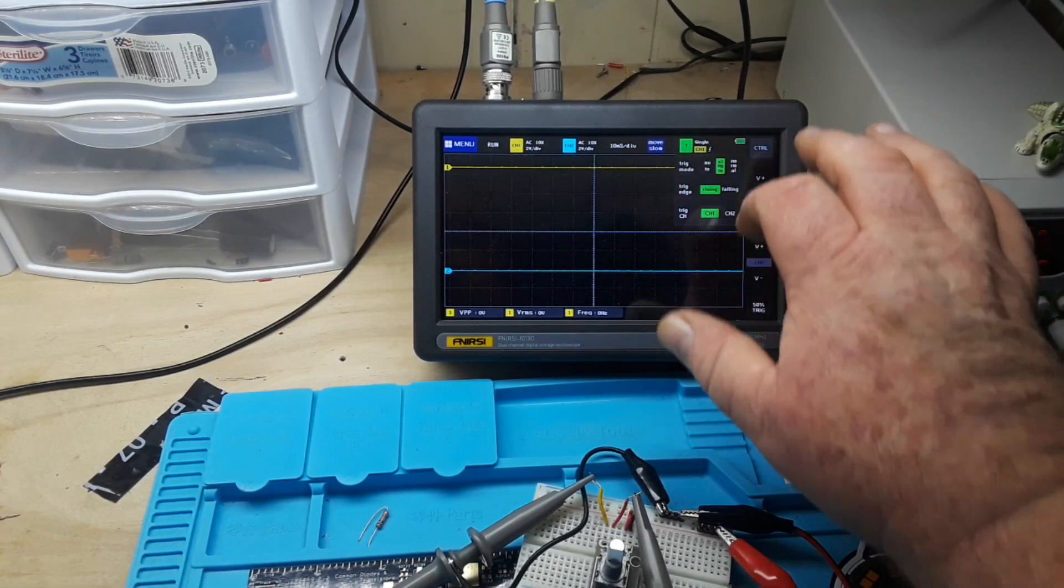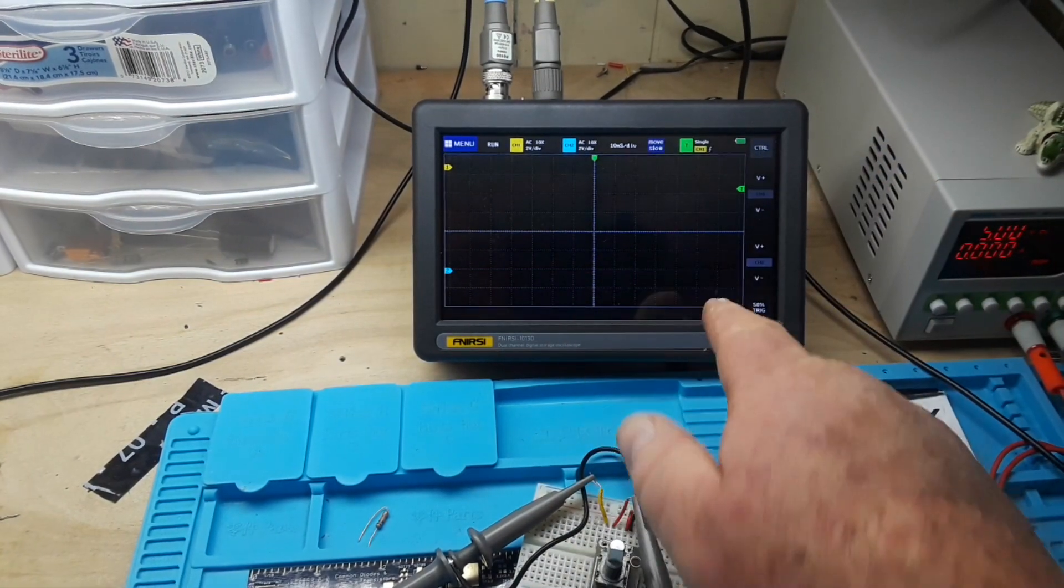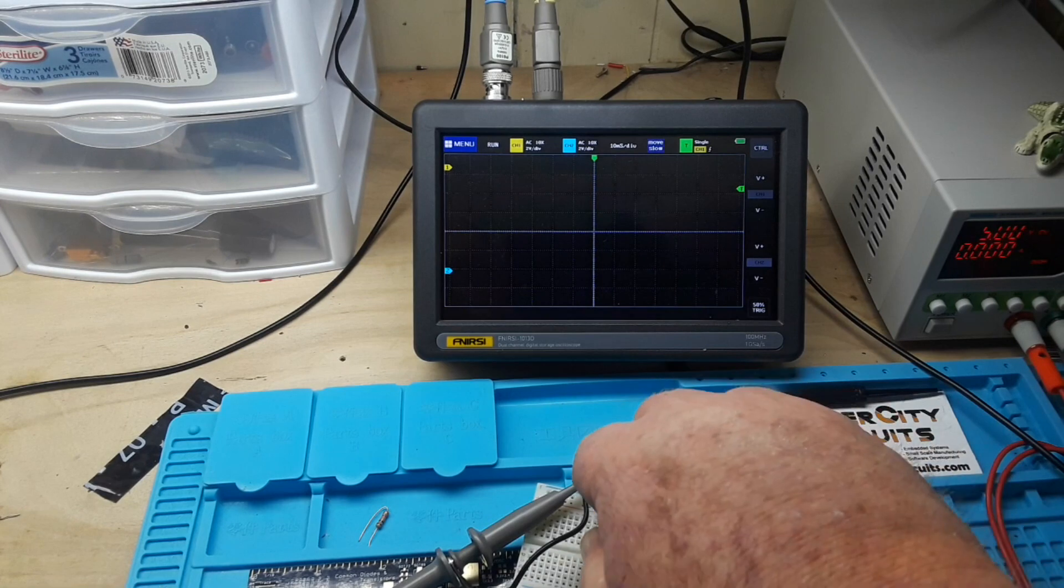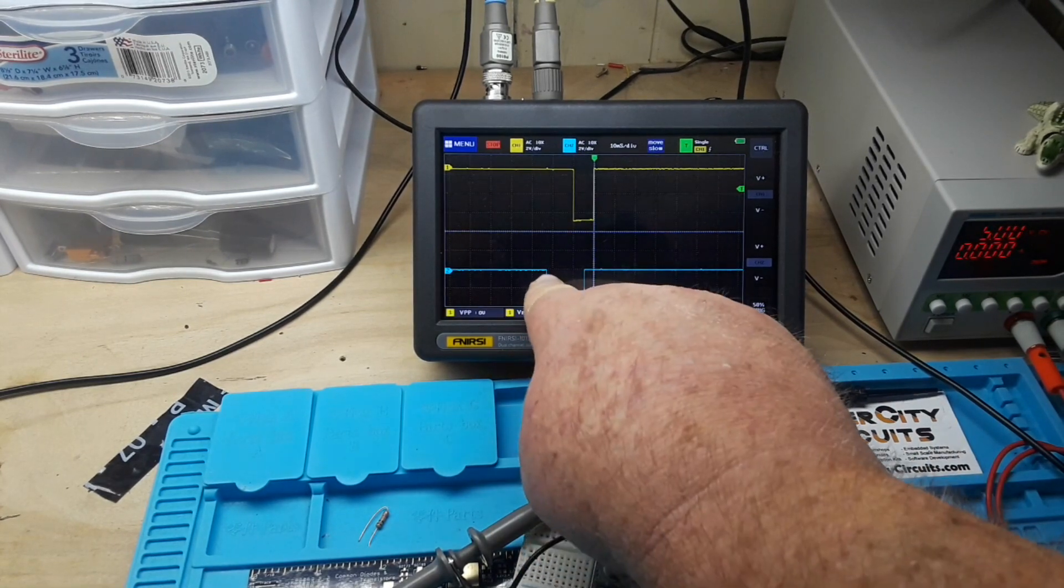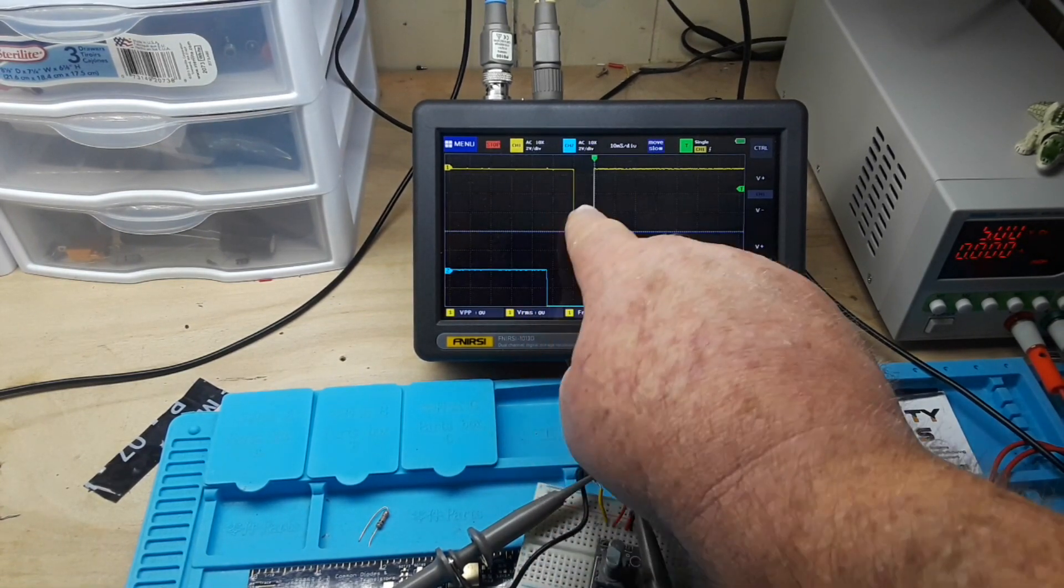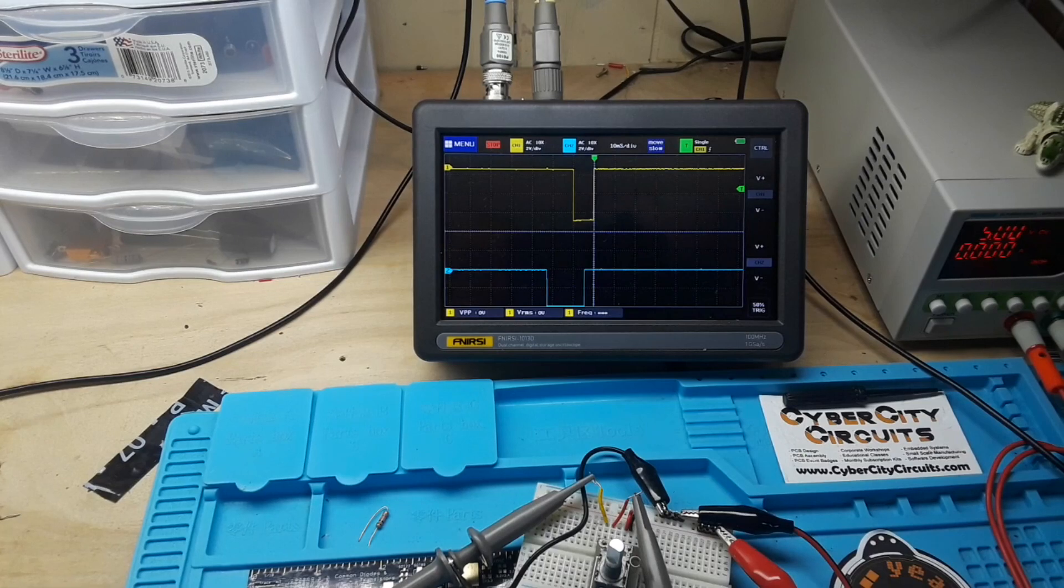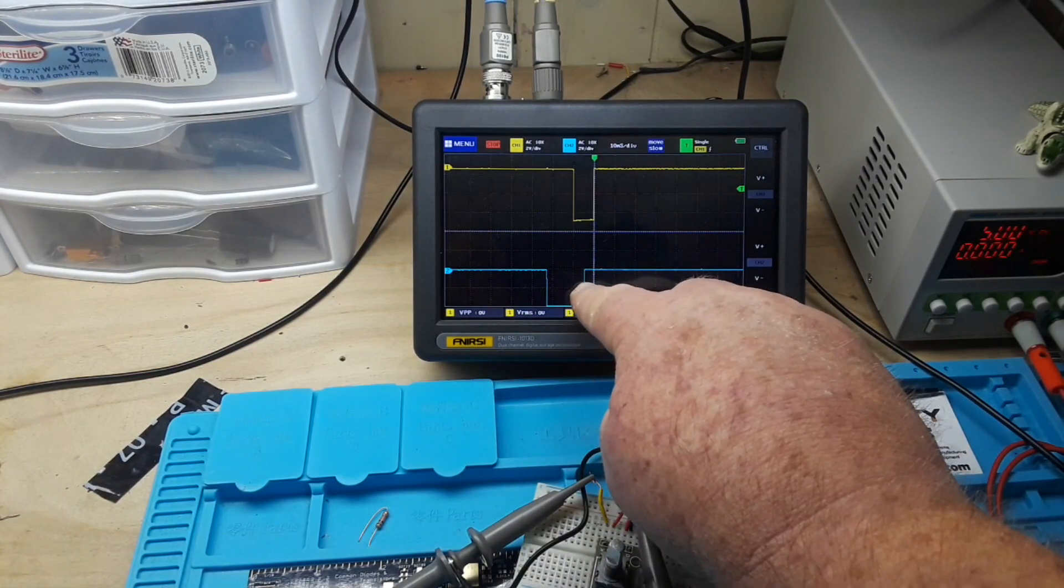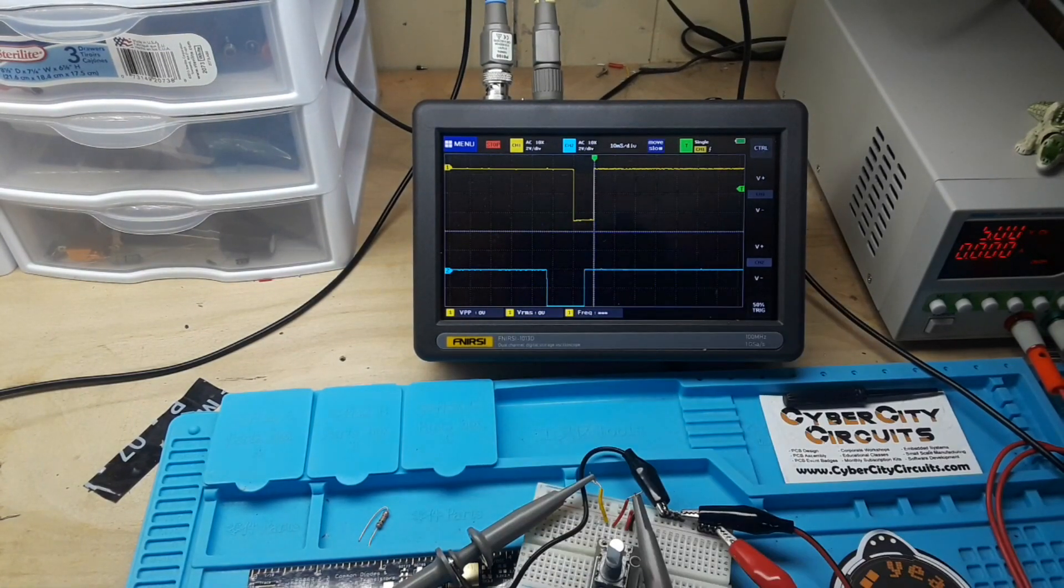You can see the yellow channel triggers first. Let me put this into a single shot mode for you. All right, I'm going to turn clockwise. And you can see the blue channel triggers before the yellow channel, so channel two is triggering first and then channel one is triggering.